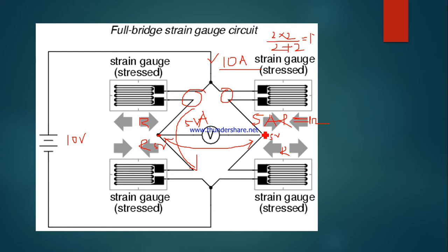You know, strain is basically measured in terms of elongation or compression. So based on the load cell type, once the compression or the tension is applied on the load cell outer body, accordingly the resistance will be changed, and you will get a potential difference between these 2 points. These 2 points are called the excitation, and these 2 points are called the measurement output.